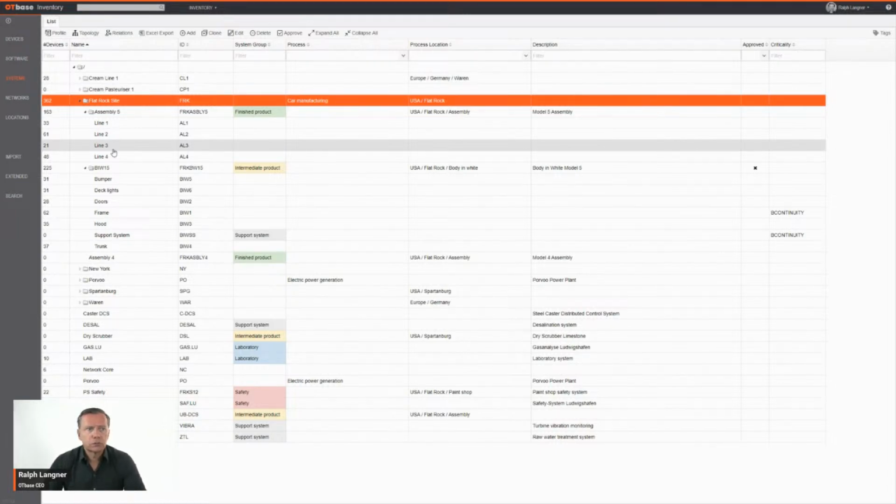So if you just consider you have a machine line 4, but some of the switches, some of the OT infrastructure for line 4 isn't in the line. You will not find it. When you go to that line, it's not there. It might be in a server room, maybe even in a different building. So this is why it's useful to separate those dimensions. On one side, you have the functional perspective, that is systems. And on the other side, you have the purely geolocational perspective, that is in the locations here.